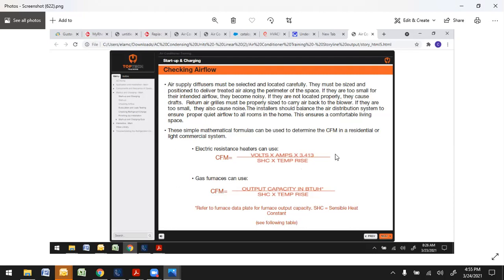Just because you have your blower set on high speed and you think it's putting out 1250 CFM, that really doesn't mean a whole lot. Yes, in theory, you're in the right ballpark. But based upon static pressure, filter drop, and all kinds of different things, you may not truly be getting what you think you're getting as far as CFM. So just a simple checkup on this. You can do this with gas furnaces or resistance. For your gas furnace, you'll take your output capacity.